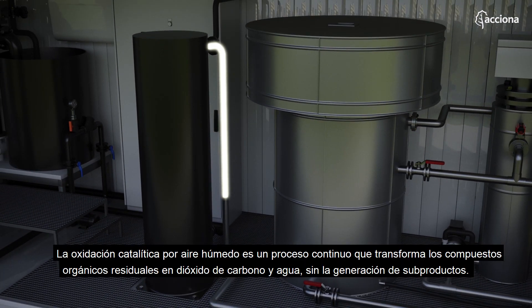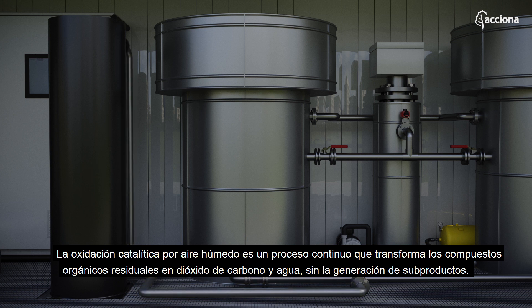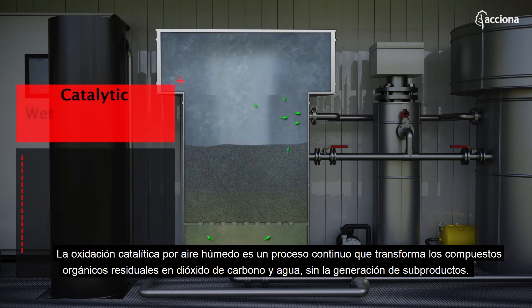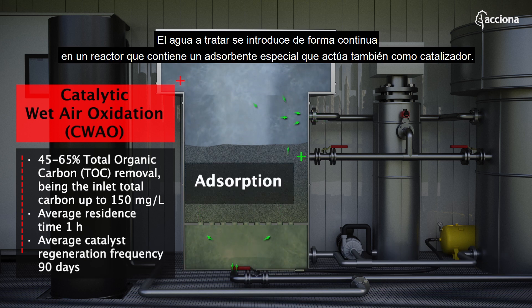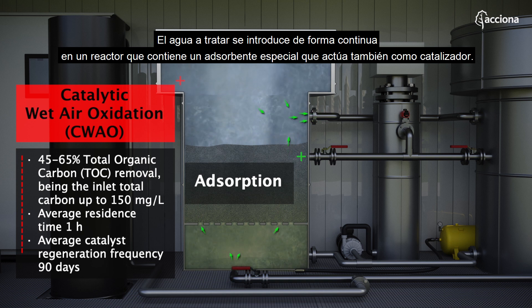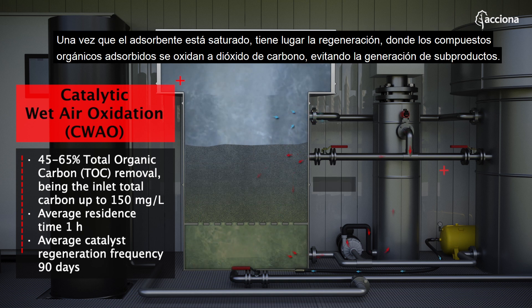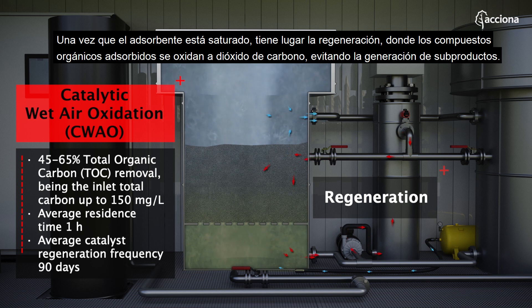Catalytic wet air oxidation is a continuous process that transforms the residual organic compounds into carbon dioxide and water without the generation of by-products. The water to be treated is introduced continuously into a reactor that contains a special adsorbent that also acts as a catalyst. Once the adsorbent is saturated, regeneration takes place, where the adsorbed organic compounds are oxidized into carbon dioxide and water, avoiding the generation of by-products.